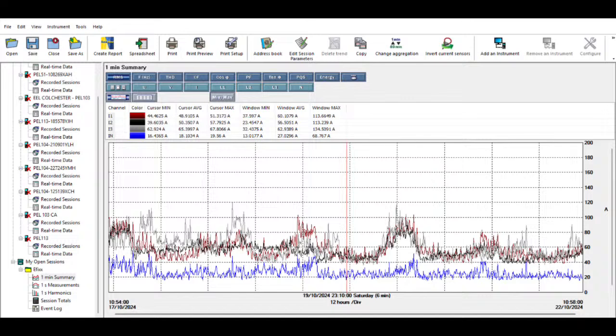Along the top we've got RMS data, and our cursor minimum - that's where the red line is. We can't do any manual adjustment since it's a screenshot, but we can also see the maximum. The maximum on L1 was 113.6649, very similar on L2, so it's quite a balanced system, and then L3 we've got 134.